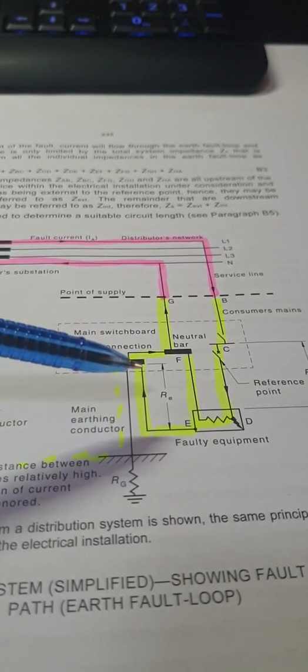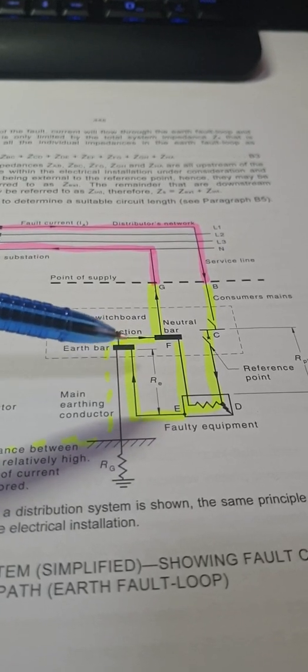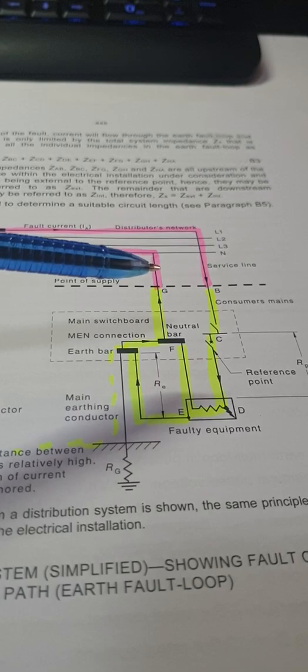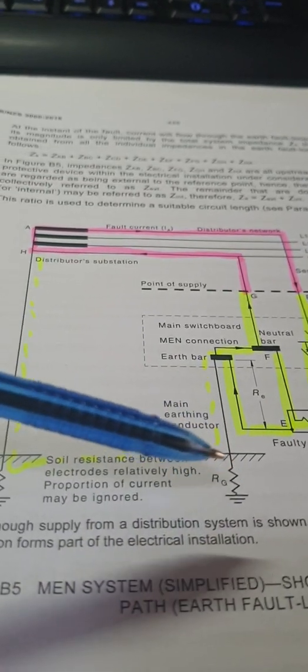So the fault loop impedance is between the supply active down through here to the earth, back here to the earth bar via the MEN link, which is this part here, and then back out again. It takes the shortest path. I'm going to do another video on why it goes back via the neutral and not back via the ground.